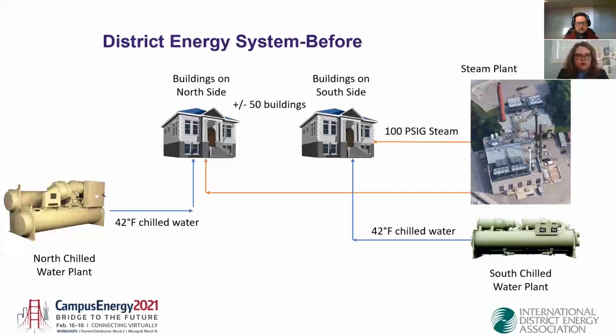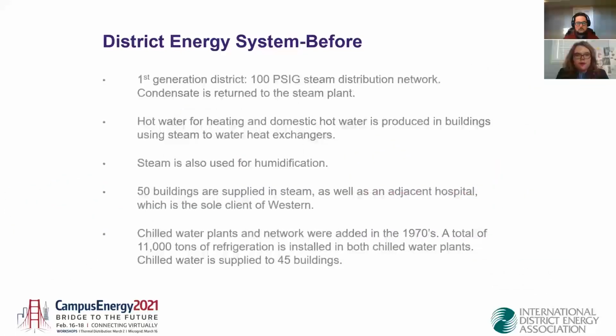Steam is used in different ways in every building, either to produce heating water, domestic hot water, or to humidify. And the chilled water was supplied at roughly 42 Fahrenheit to every building. Both plants come online in May, and they shut down around mid-October to the beginning of November. So as I said, it was a first generation district, with 100 PSIG steam distribution, and the condensate is returned to the steam plant. Hot water for heating and domestic hot water are produced in buildings, so there are heat exchangers in every building.